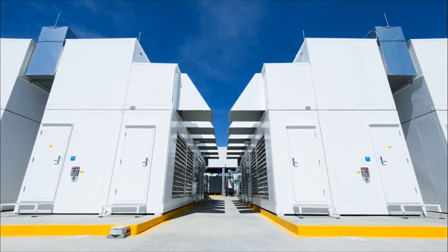Essentially, the air is flowing through the data center. The servers are naturally sucking through that air, and as the air is heated up, it gets pulled out of the top. Just pulling the air out of the top keeps that airflow going through the data center and keeps it cool without having to use any power other than to operate the monitoring technologies or open the vents to control the temperature. So it's a really efficient way of doing it.